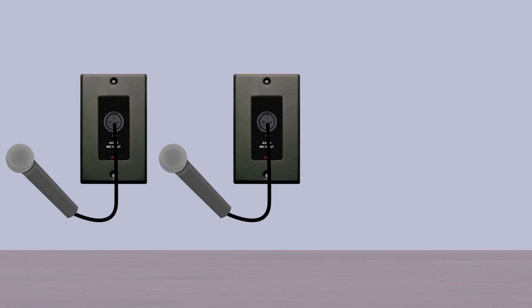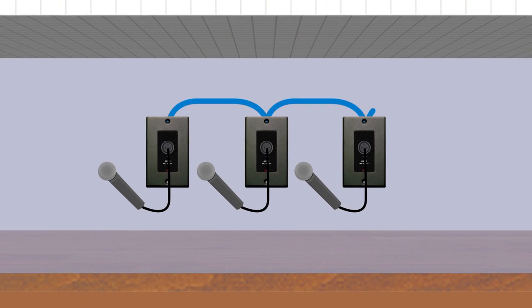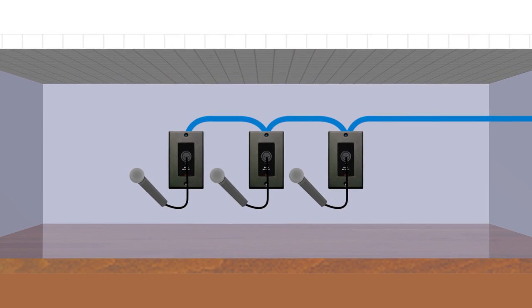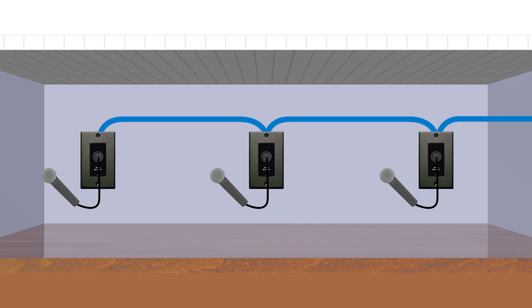Audio sources connect to Format-A senders. Up to three single-pair senders can feed a single twisted pair cable run. The senders do not need to be located together. In fact, each sender may be in a different location or even in a different room.